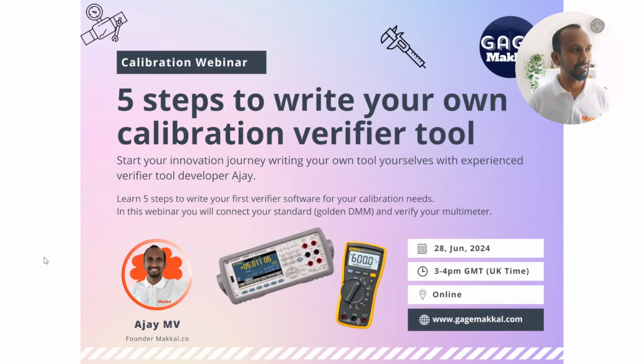So we will look at the 5 steps to write your own calibration verifier. In many cases, when we start the calibration, before we even do the calibration, what we need to do is something called verification. So we need a verification tool that lets us verify whether the instrument is ready for calibration, needs a calibration, or we are okay with the current tolerance levels.